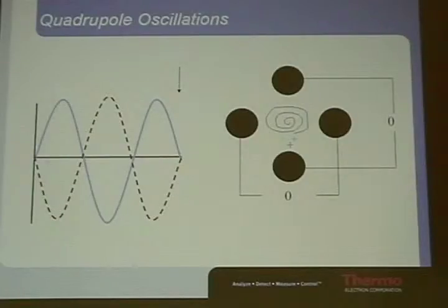Well, we have that problem and we don't want that problem. The minute they come out through that small hole, we have this nice tight packet of ions and the packet goes whoosh, just like that. And if we don't refocus them, we're going to lose those ions. They have to physically get to the next hole. So the ions come out of that small hole, they supersonically expand into the opening of these multipoles.